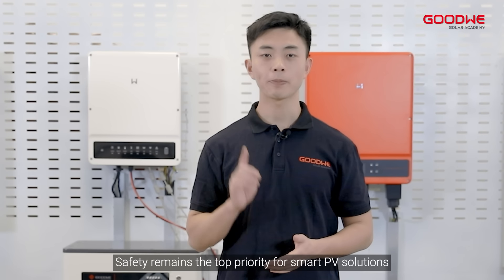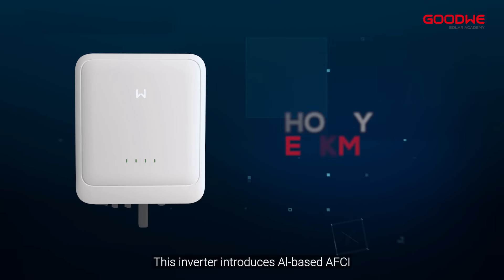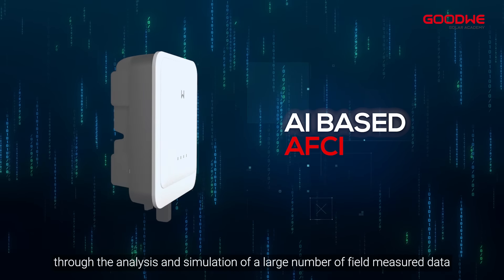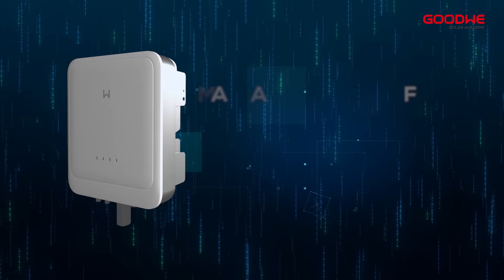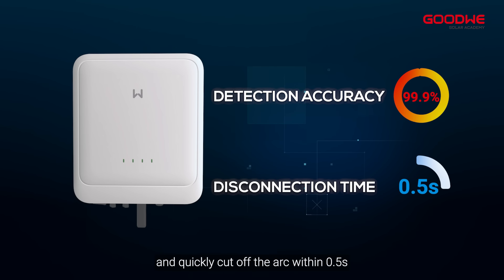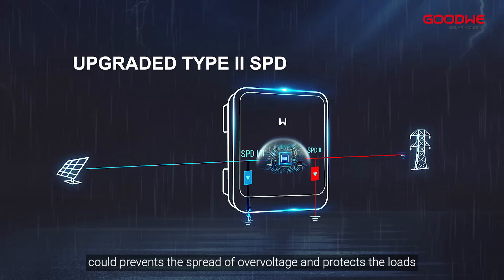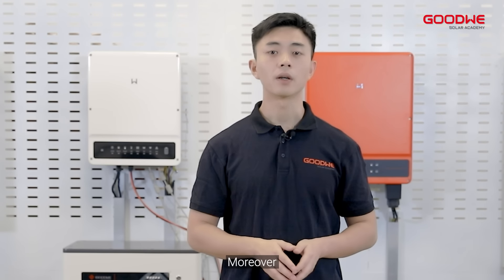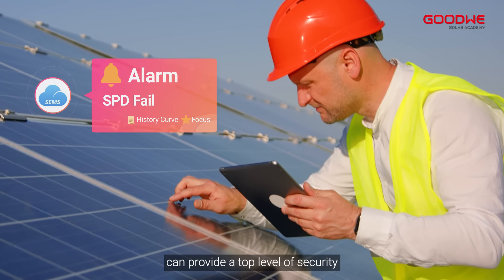Safety remains the top priority for smart PV solutions in a residential scenario. This inverter introduces AI-based AFCI through the analysis and simulation of a large number of field-measured data. GoodWe AFCI can accurately identify and quickly cut off the arc within 0.5 seconds. The upgraded optional Type 2 SPD on both DC and AC side could prevent the spread of over-voltage and protect the loads. Moreover, the optional SPD failure alarm on the DC side can provide a top level of security.